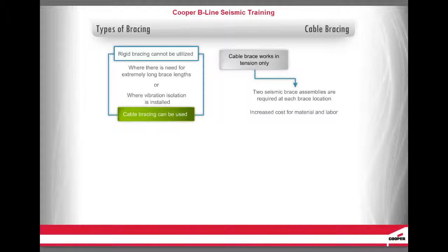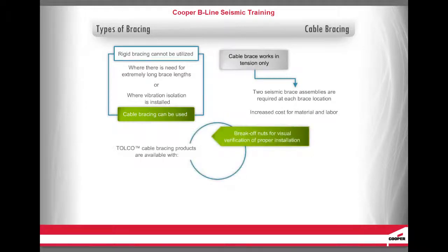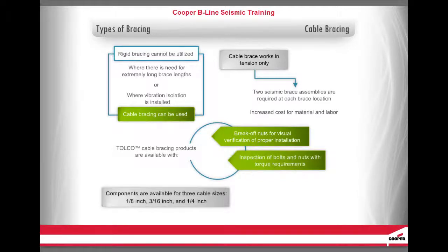As with rigid bracing, Tolco cable bracing products are also available with break-off nuts for visual verification of proper installation, and inspection of bolts and nuts which have torque requirements. The components are available for three cable sizes: 1/8 inch, 3/16 inch, and 1/4 inch. The larger the cable diameter, the greater the load capacity.